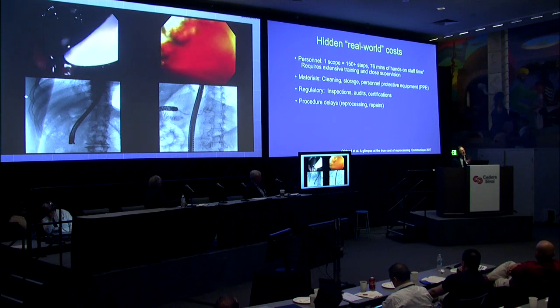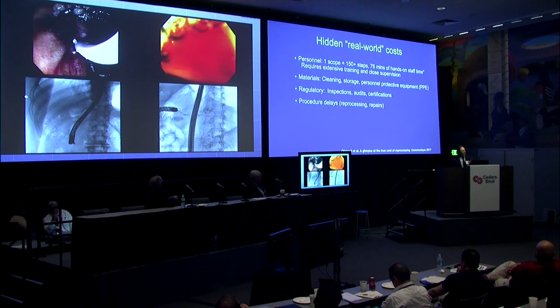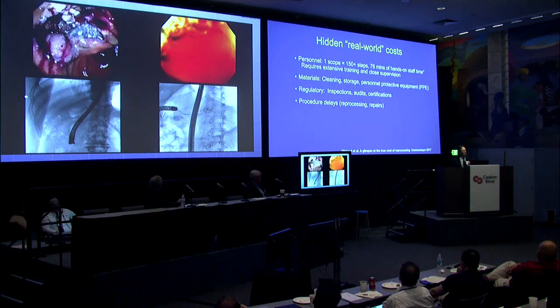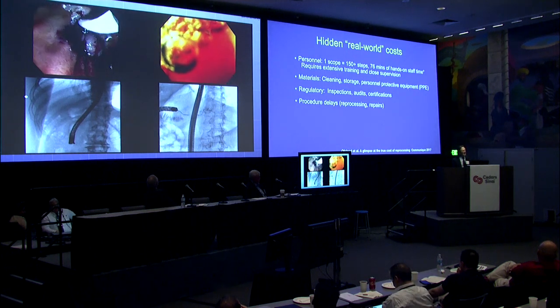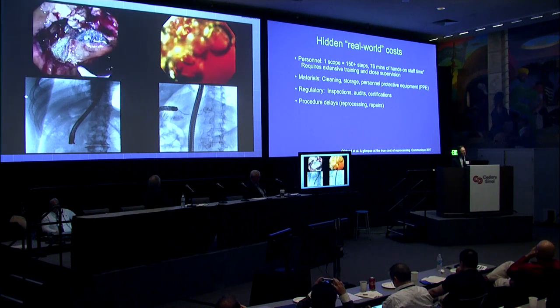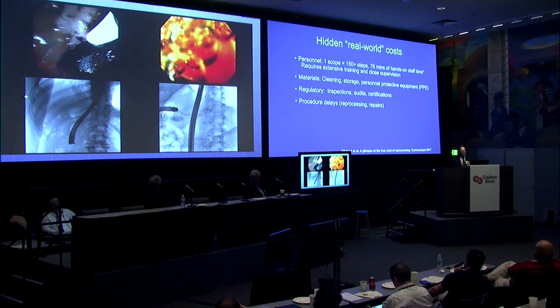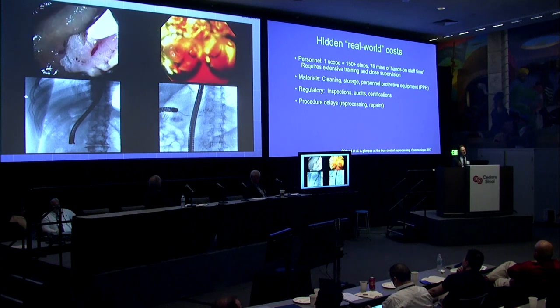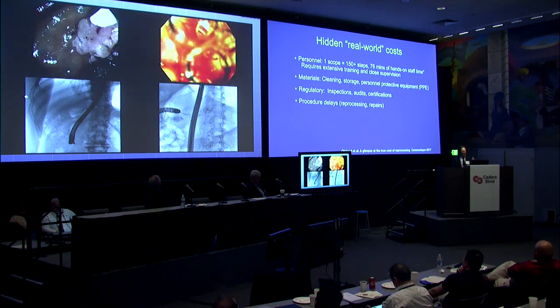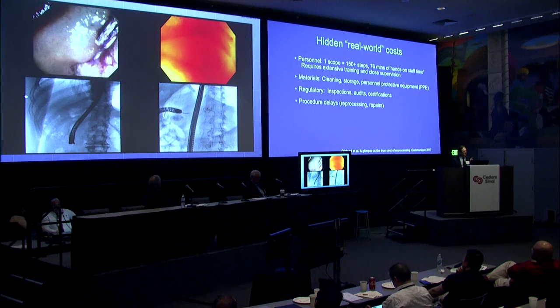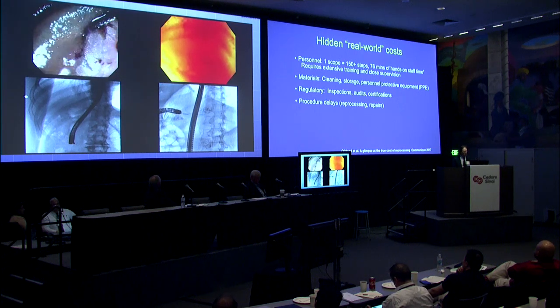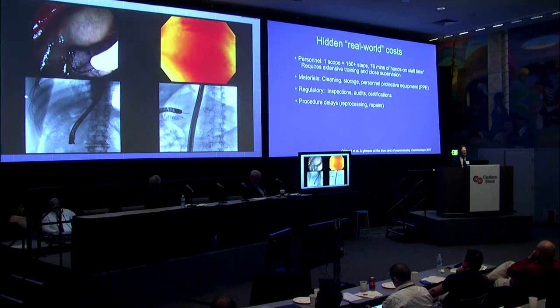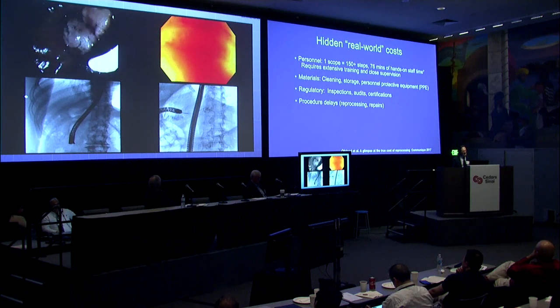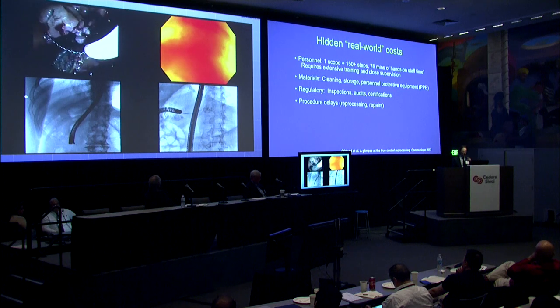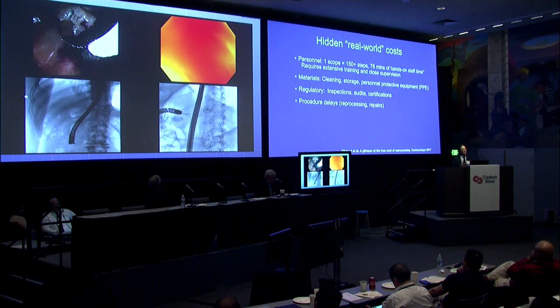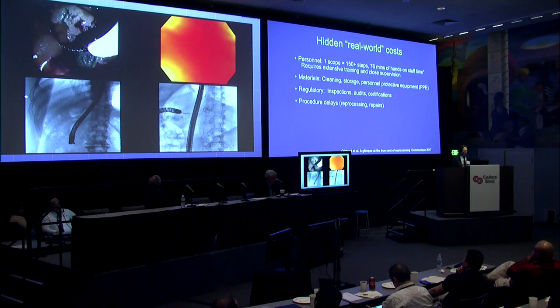But if it's going to be higher than that, you have to account for all the hidden real-world costs, because the amount of intensity required to clean these scopes is mind-boggling. Looking at the 150 steps the personnel have to go through, with a minimum of 76 minutes, over an hour per scope, of hands-on staff time for cleaning. It requires extensive training and close supervision, and there's actually a lot of turnover among this personnel because they're exposed to these toxins the whole day.